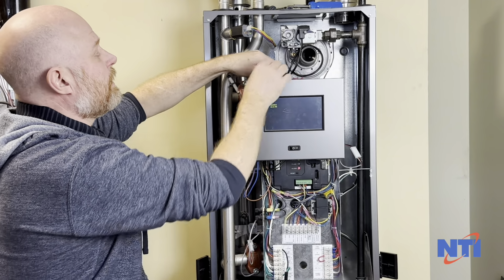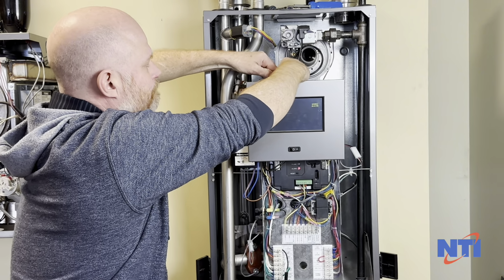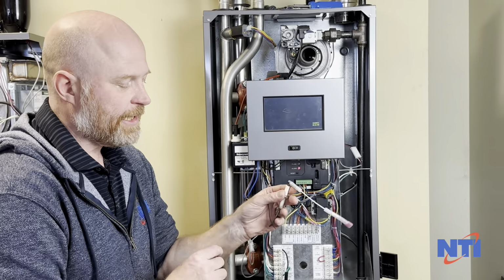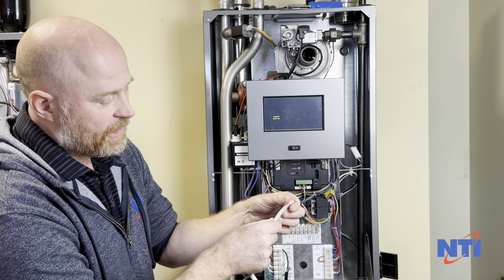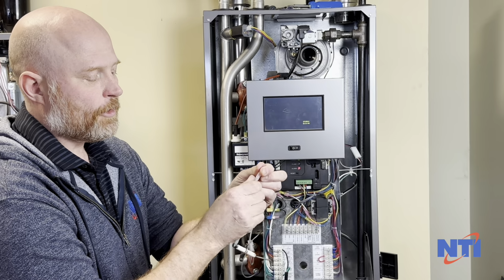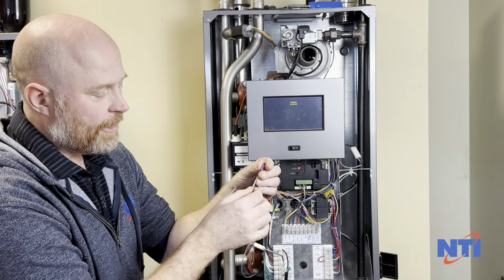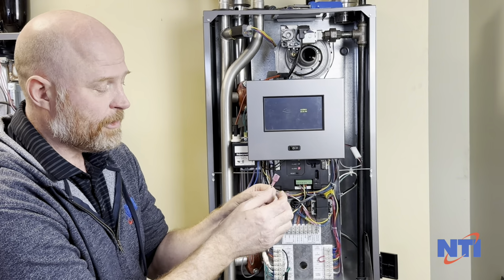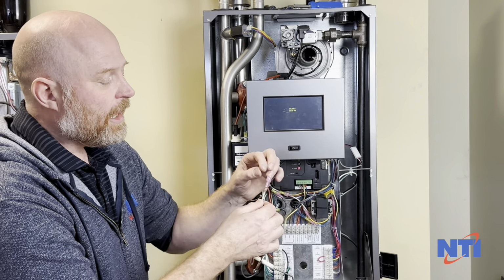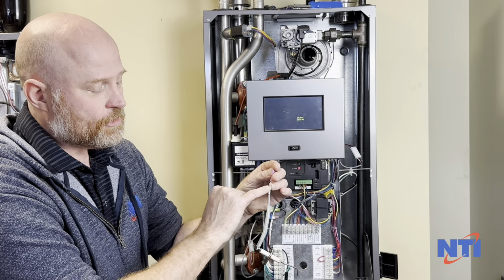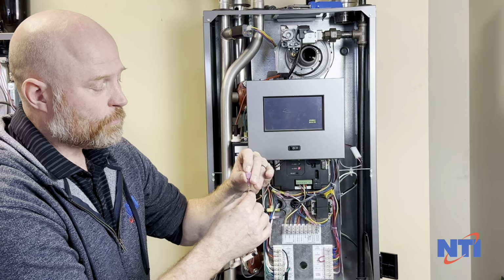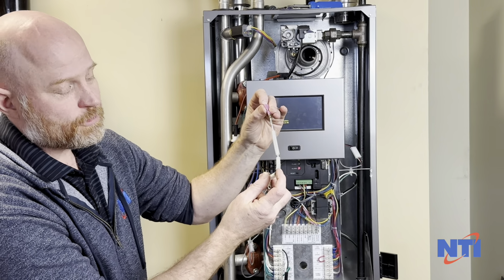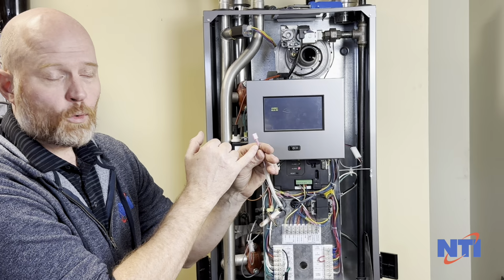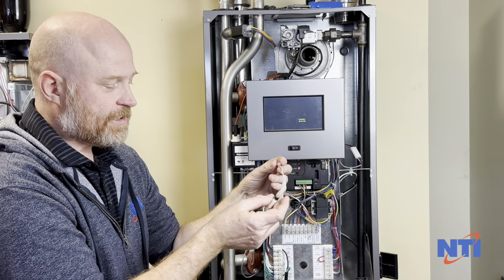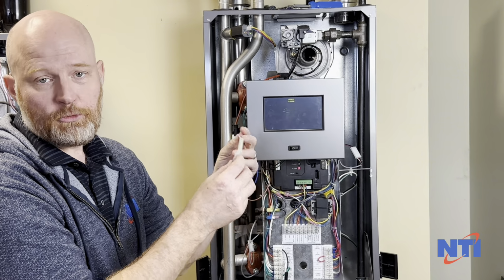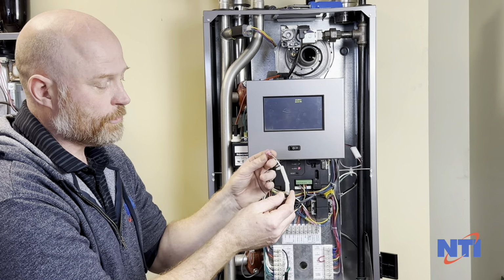Another thing to inspect, and this is going to vary a little bit based on the model. So once you've removed your igniter, have a look at the cable here. Some of these cables, especially if they have this silicone tubing on them, are going to have resistors built in. They're there to actually reduce the flame signal or make it a bit weaker, and that has to do with the flame safety on the boiler. I have seen rare cases where as these age, they just don't make a great contact. So you're going to measure for resistance from this part of the harness through to the tip here. And the resistance range you're looking for is somewhere in the mega ohm range. So that's going to be, could be 500,000 ohms. It could be as high as 2 million ohms. It depends on the boiler that you're working with.